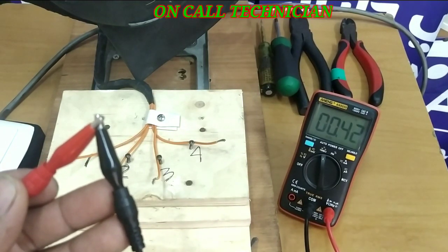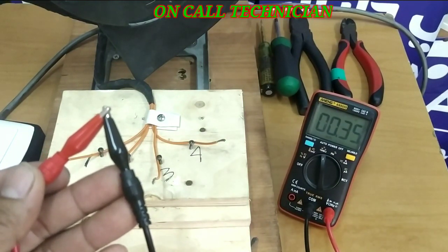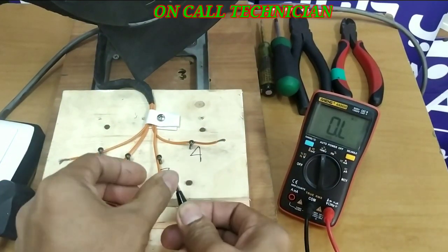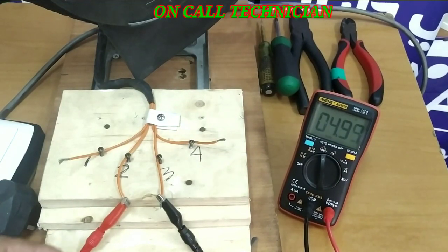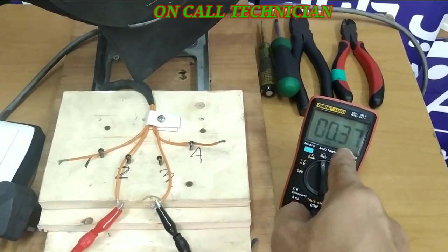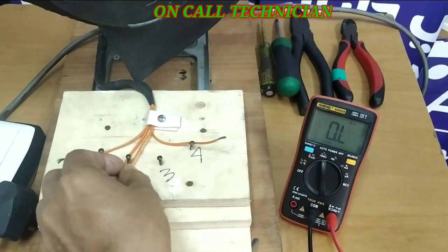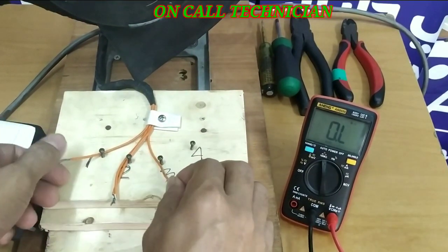Take note, guys — these two terminals are almost shorted; there's a slight difference in the reading because it is wired in series inside the fan motor. When I short this test probe and put it between terminals two and three, the reading is 0.37 ohms, meaning this wire is a jumper wire. Now we have only three wires.